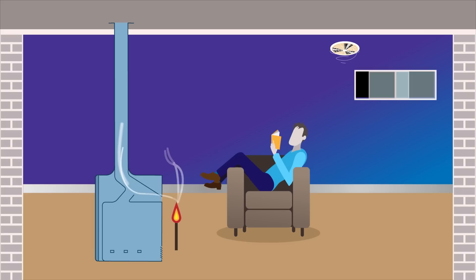Please be mindful that on windy days you may see intermittent disturbances of smoke at the draft diverter from wind gusts at the flue cowl. This is not a sign of negative pressure. Negative pressure will draw a constant stream of smoke away from the heater.